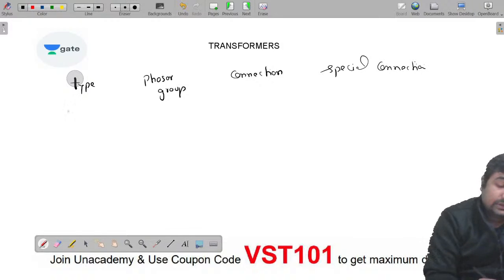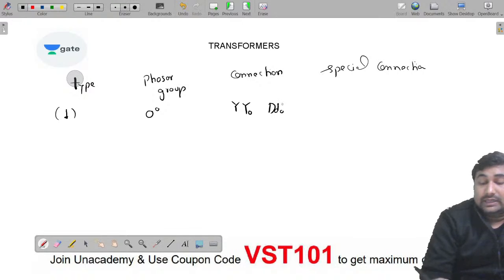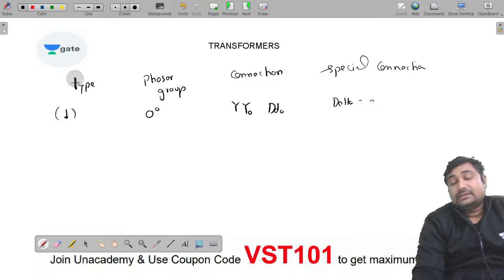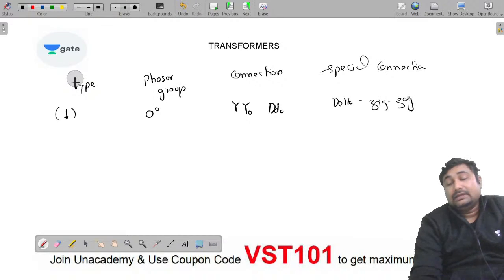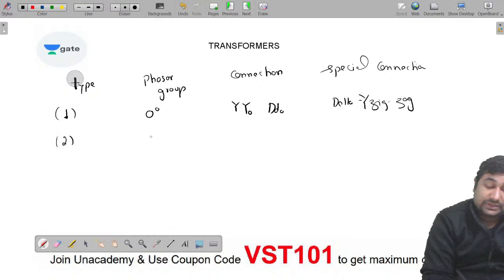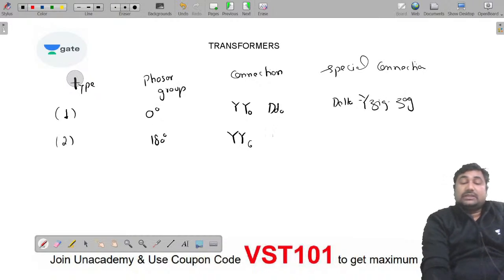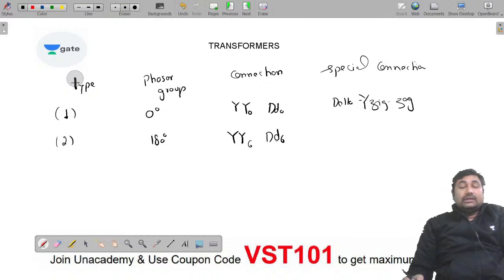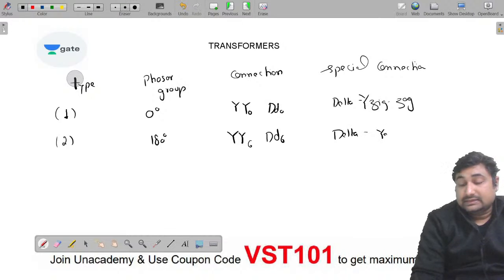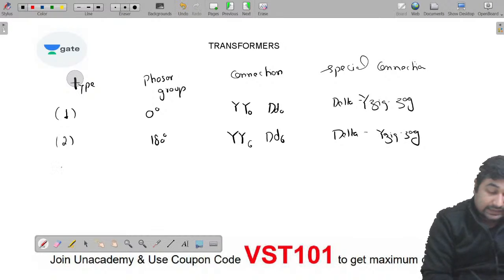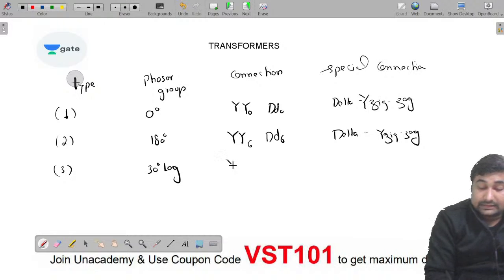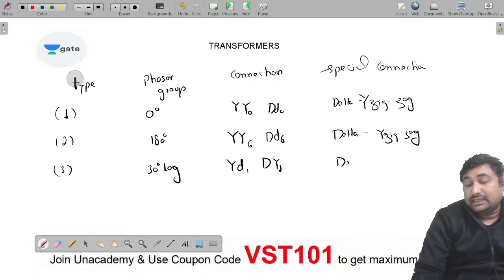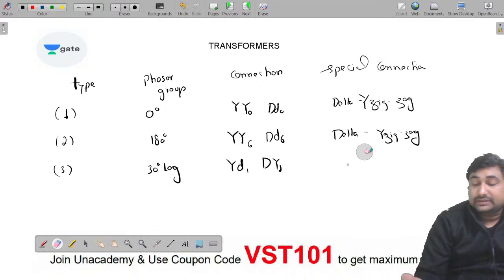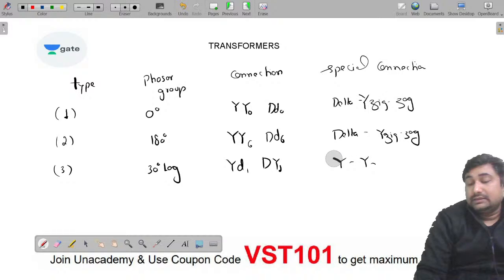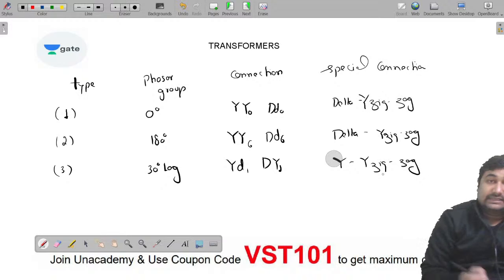Type 1 phasor group is 0. Connections are star-0 and delta-0, and special connections are delta-zigzag-star or delta-star-zigzag. Second is type 2, the 180-degree connection, which includes star-6 and delta-6, with special connections delta-zigzag-star. Third is the 30-degree lag, that is star-delta-1 and delta-star-1, which includes the star-zigzag connection. The secondary is always zigzag, and that secondary is in star.